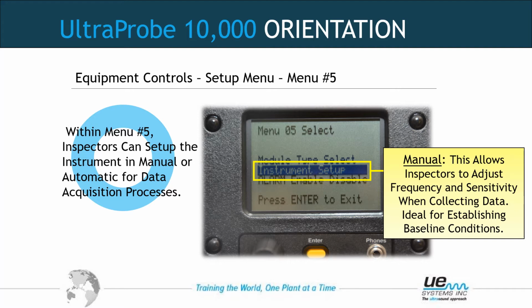If the unit is in automatic, when you reload that route for the second, third, fourth, whatever time, it will preset the unit to the frequency and sensitivity that it was set to during baseline, very important during trending, as well as bring over all the input information that you entered either in the software or in the instrument when you were in the field. If the unit was in manual, it would not do those things. It's important that the unit is in manual when baselining.